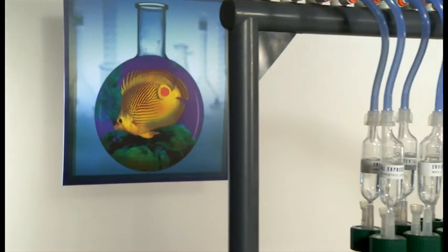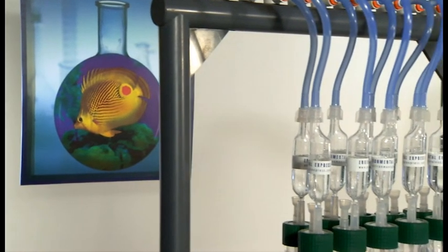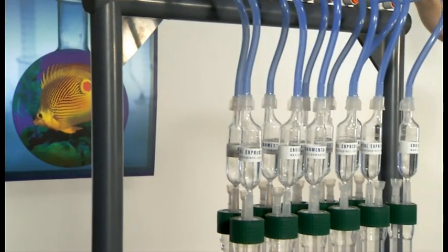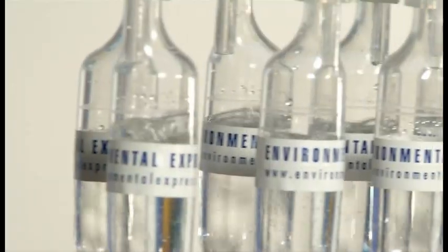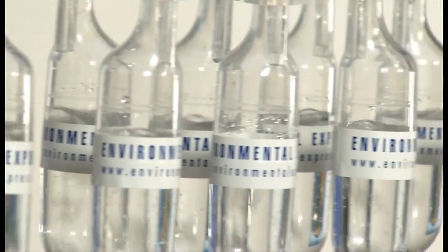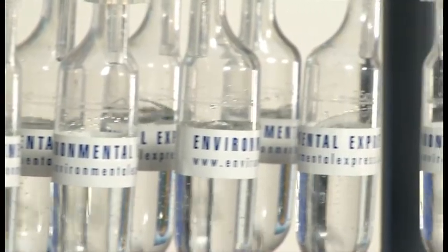The vacuum should be somewhere between 10 and 15 bubbles per second and may be adjusted using the white knobs on top of the manifold. If any reagents need to be added to the sample, now is the time to do so through the reagent addition tube.